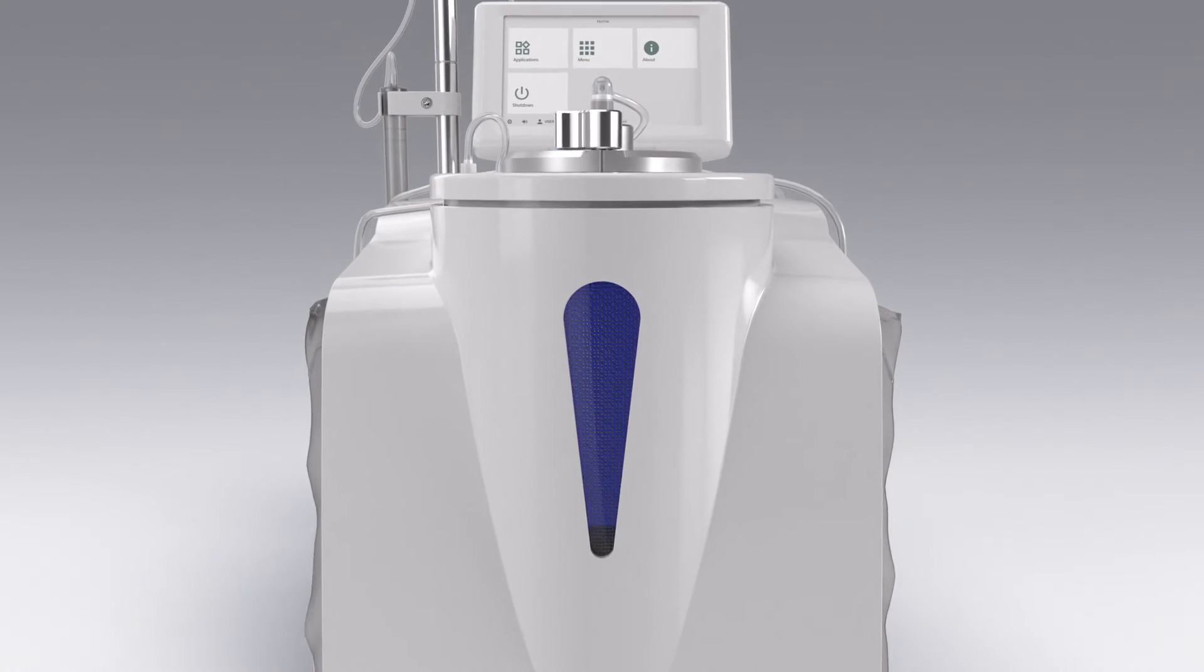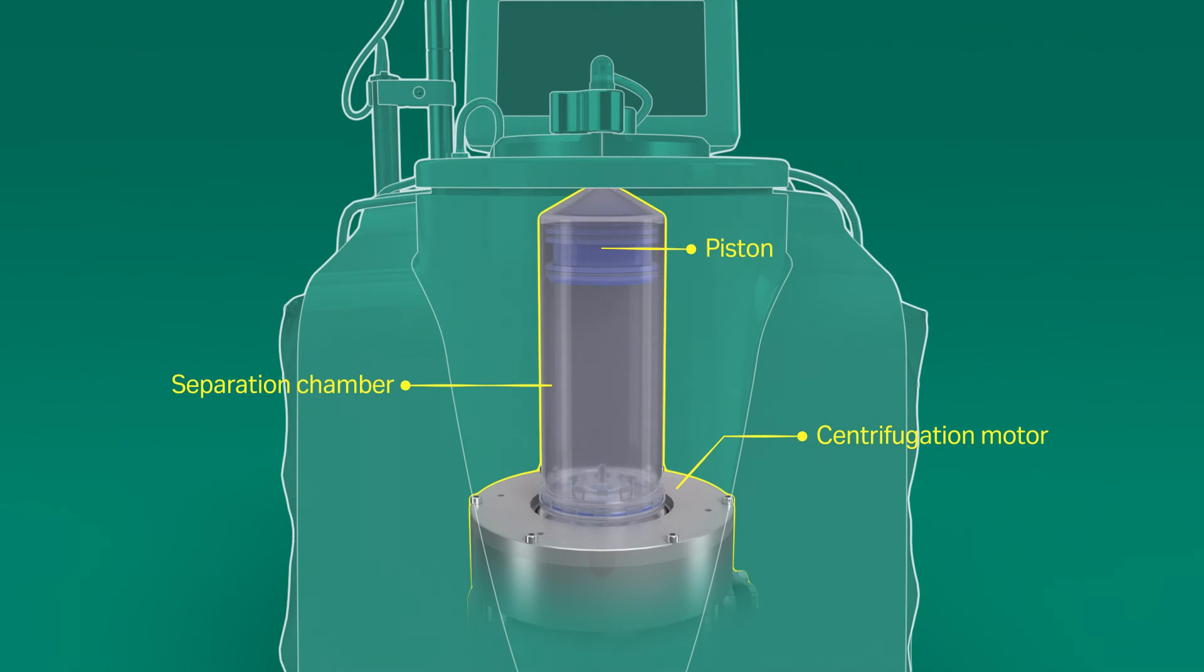The electric centrifugation motor and pneumatic circuitry drive the separation chamber piston to enable filling, centrifugation, and extraction steps using the single-use kit's separation chamber.